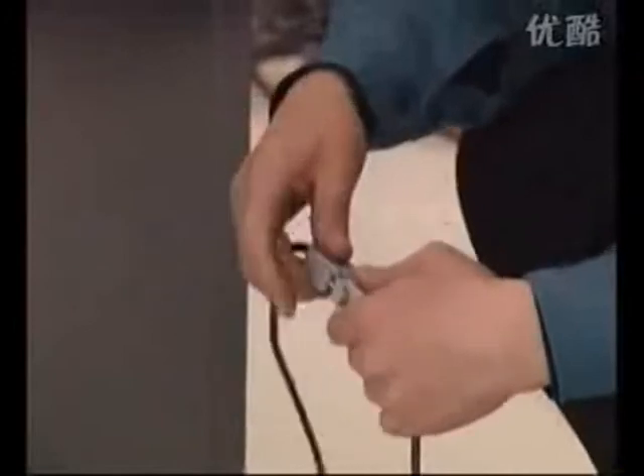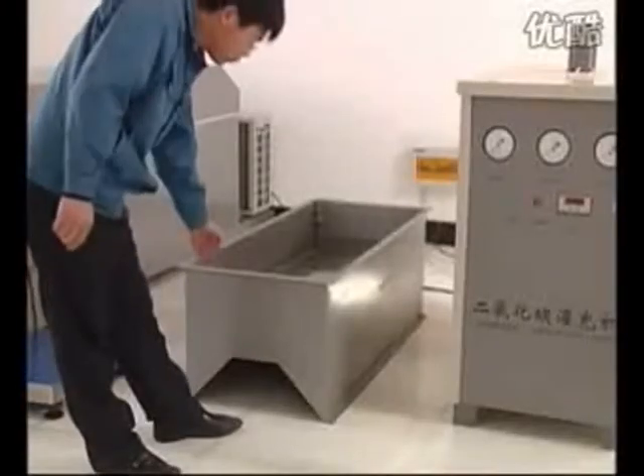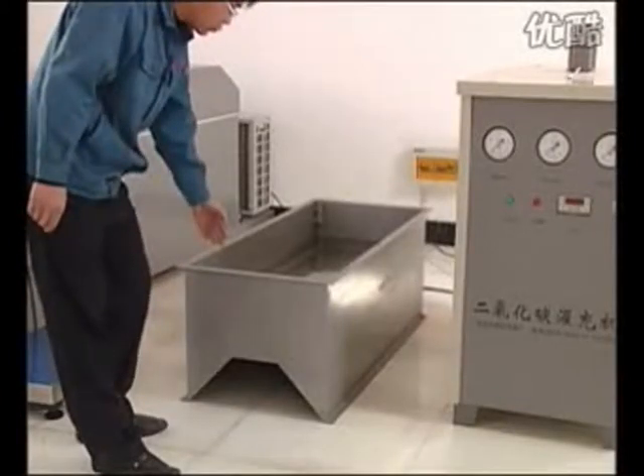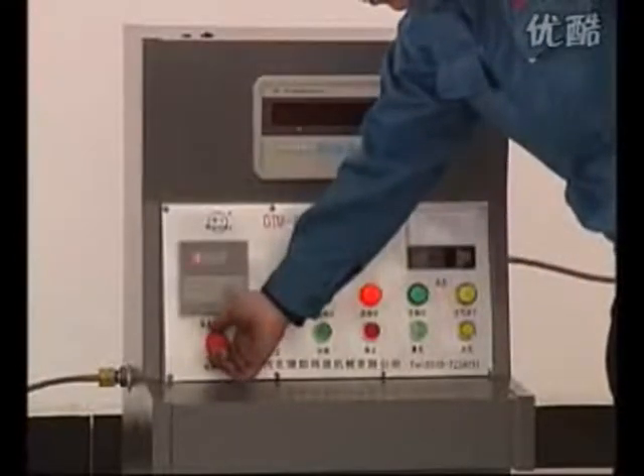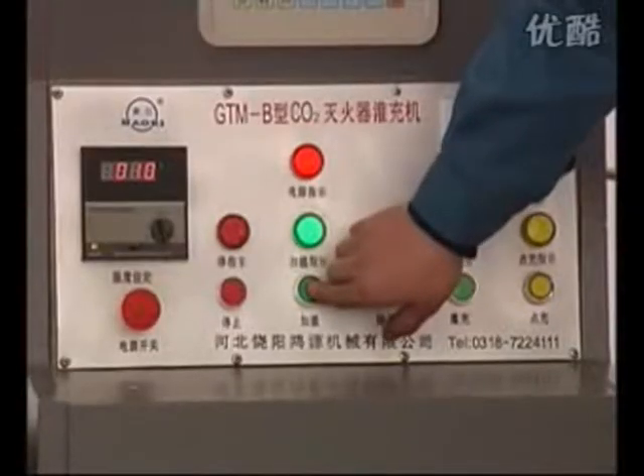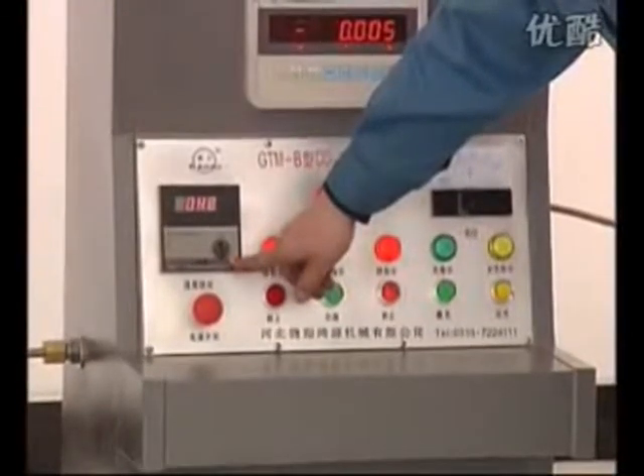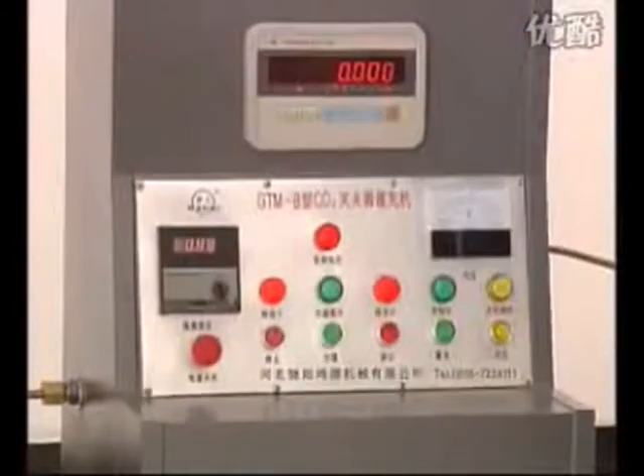Connect the pressure sensor line with the electronic scale. Put the carbon dioxide gas source cylinder into the heating water tank. Fill with enough water in the heating tank. Open the power source of the filling console, operate the temperature controller, set the heating temperature point, press the heating on button to begin to heat. When the temperature arrives at the set temperature, heating will automatically stop.